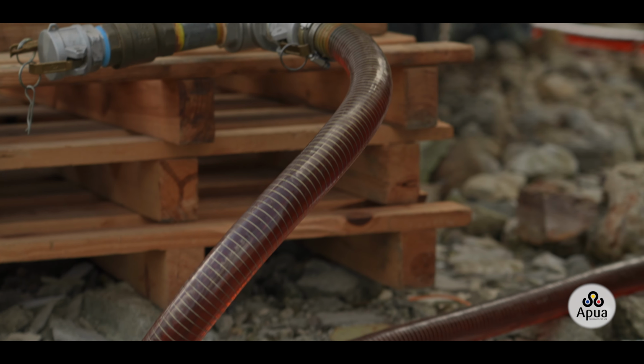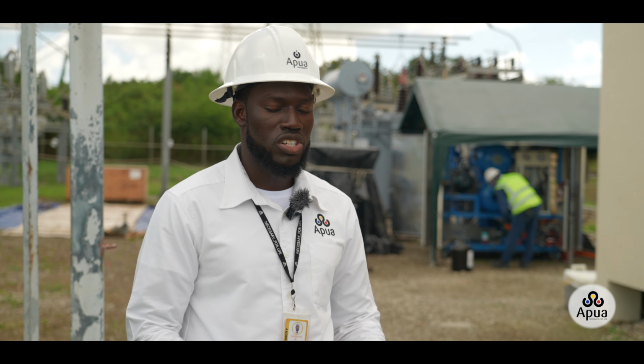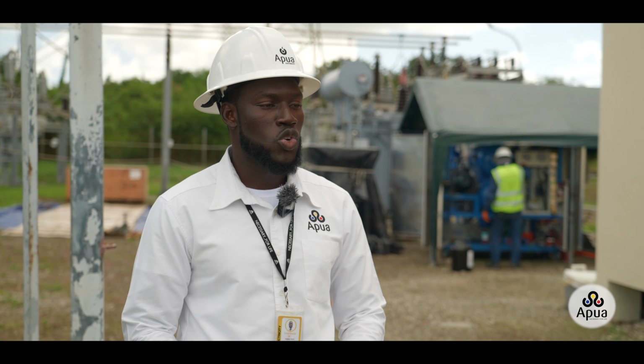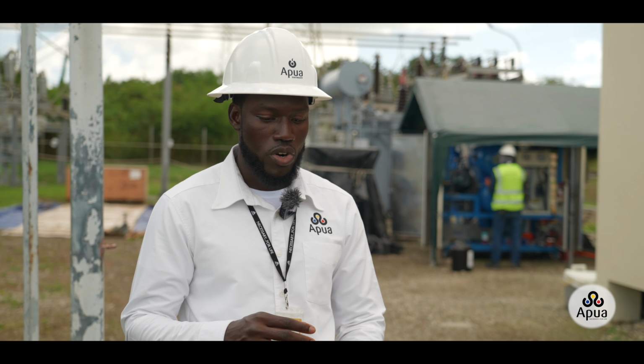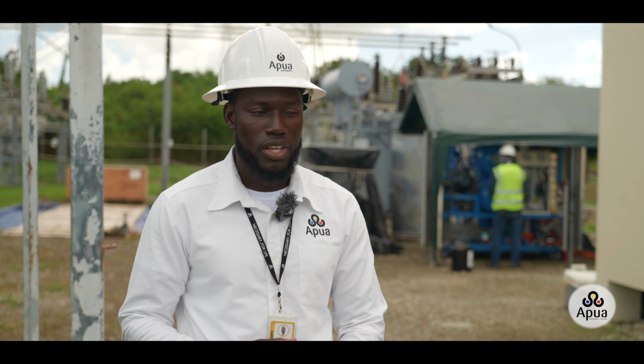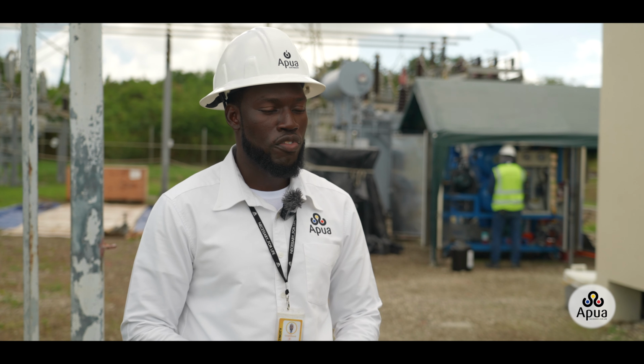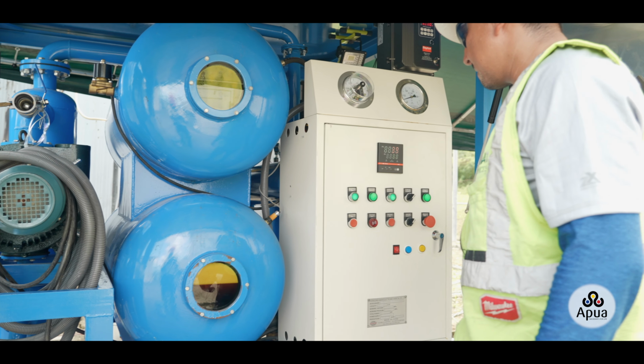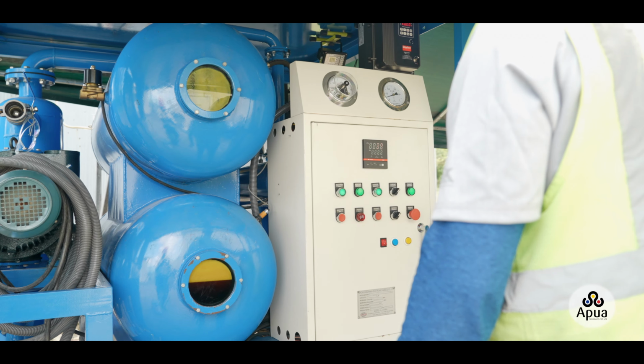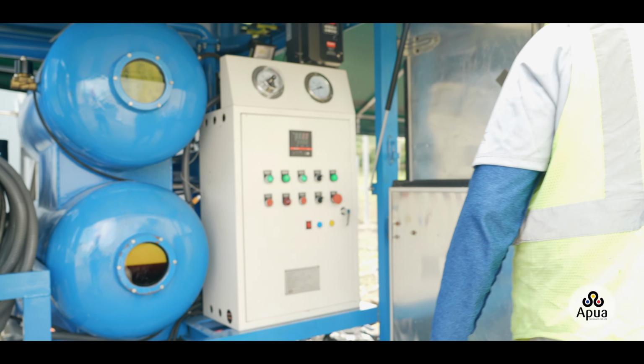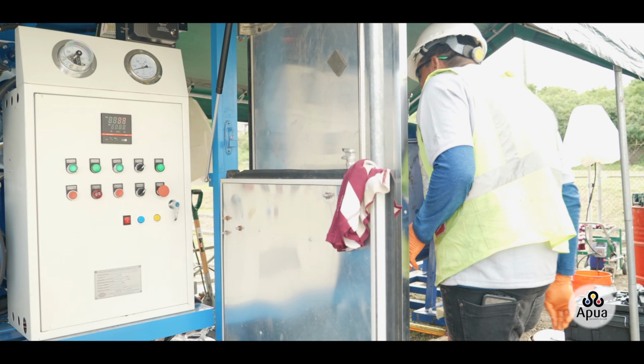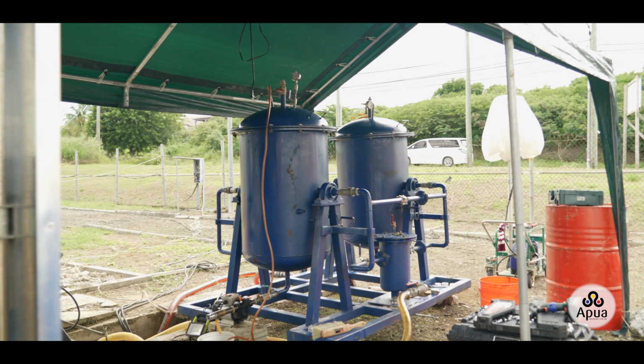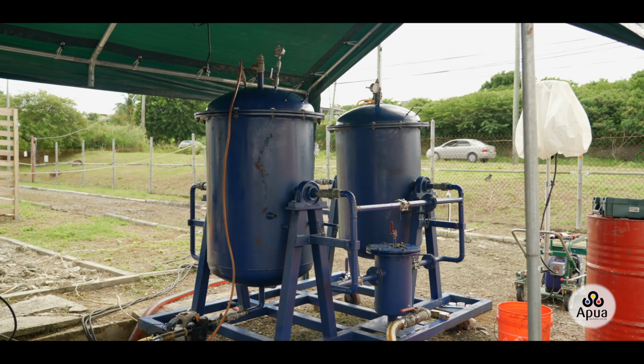During the process, the first stage, after initial setups and testing, we take a sample of the oil to know what our initial condition is. The second step is that we pass the oil from the oil treatment machine to what's called our percolator machine, which has a medium inside of it as a filter. We pass that oil over a period of 3 consecutive days, and we change that medium every 5 hours.